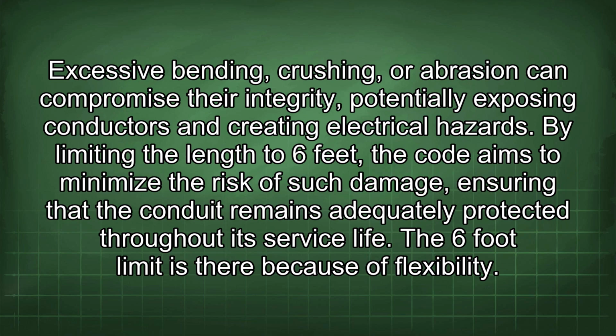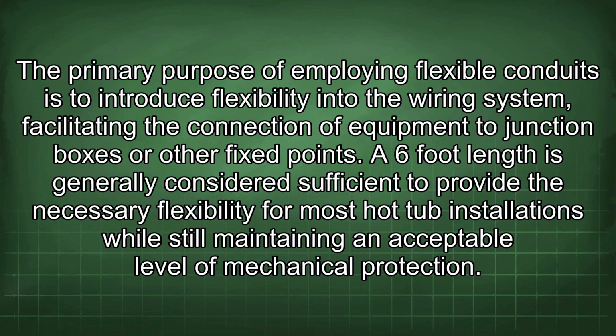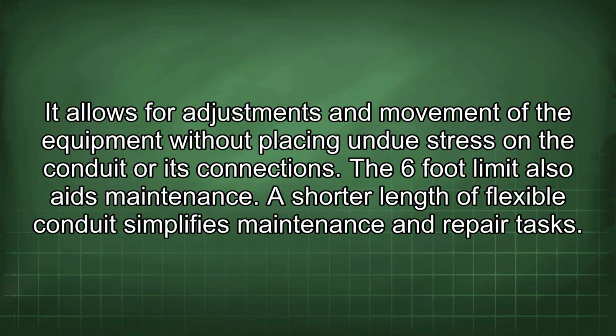The 6-foot limit is there because of flexibility. The primary purpose of employing flexible conduits is to introduce flexibility into the wiring system, facilitating the connection of equipment to junction boxes or other fixed points. A 6-foot length is generally considered sufficient to provide the necessary flexibility for most hot tub installations while still maintaining an acceptable level of mechanical protection. It allows for adjustments and movement of the equipment without placing undue stress on the conduit or its connections.